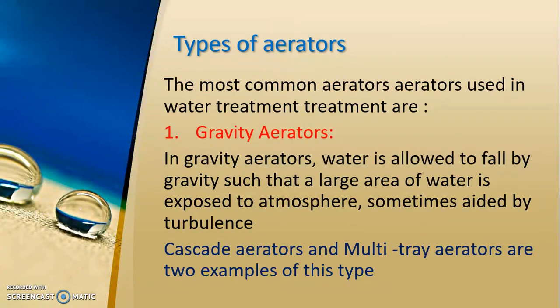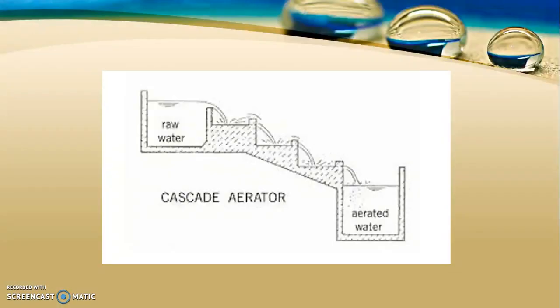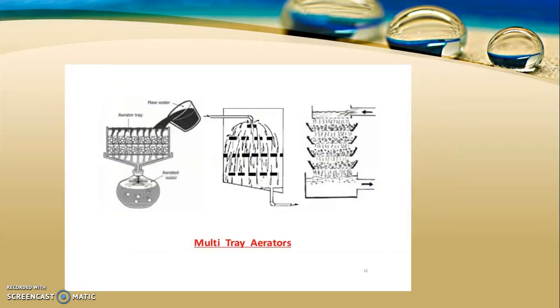There are different types of aerators used in water treatment plants. The most common are gravity aerators, where water falls by gravity so that a large area is exposed to the atmosphere, sometimes aided by turbulence. Gravity aerators include cascade aerators and multi-tray aerators. In a cascade aerator, steps are provided and water falls through them by gravity, exposing it to the atmosphere. In a multi-tray aerator, water is made to fall through a series of trays.